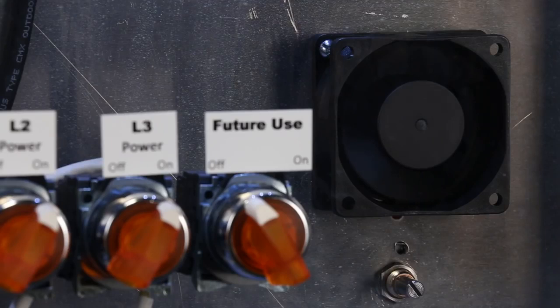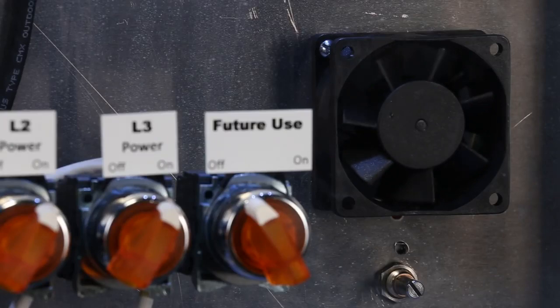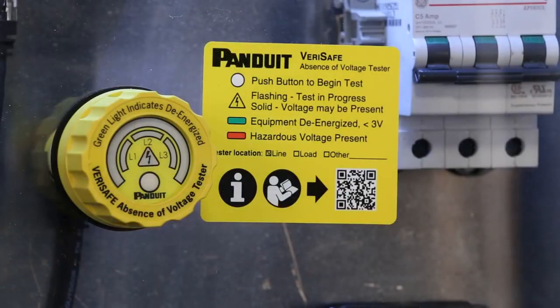In this case, there is still DC voltage in the system, illustrated by this cooling fan still turning. Once the fan stops turning, we can try the test again. This time we get the green light, which means that the AVT has verified the absence of voltage in the equipment.